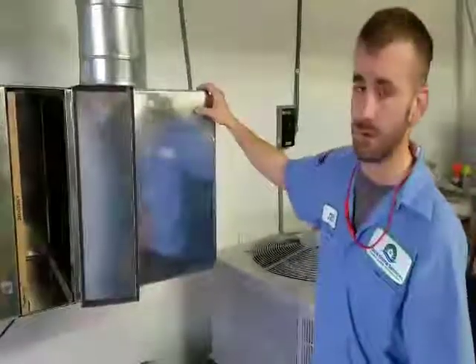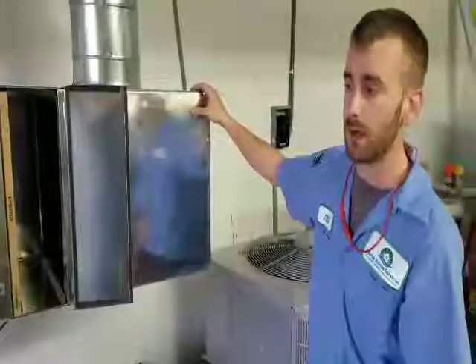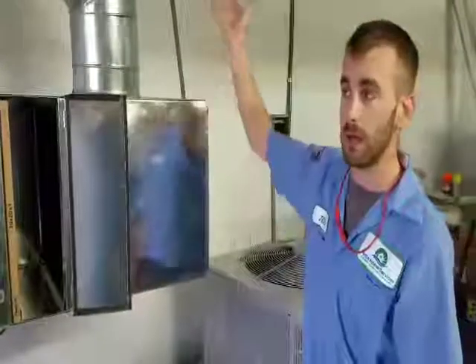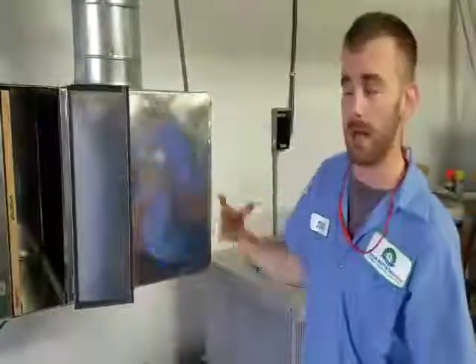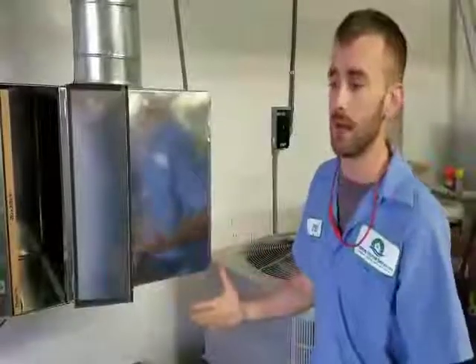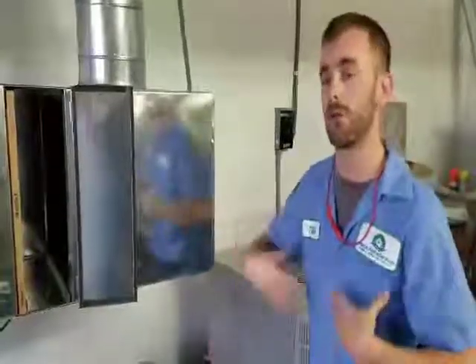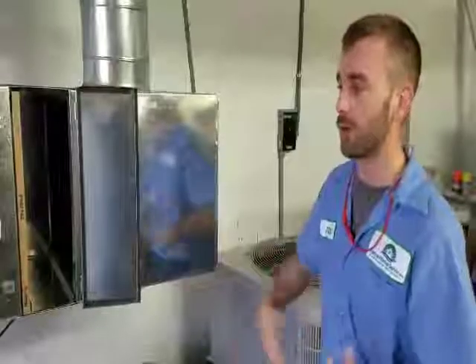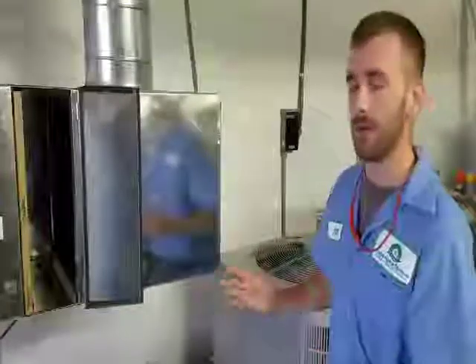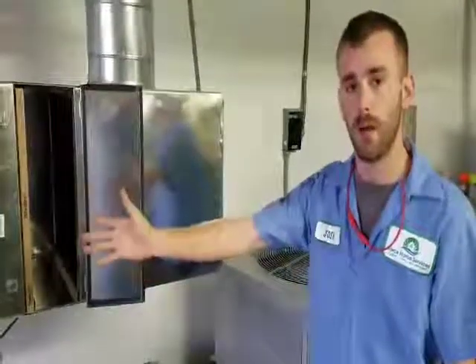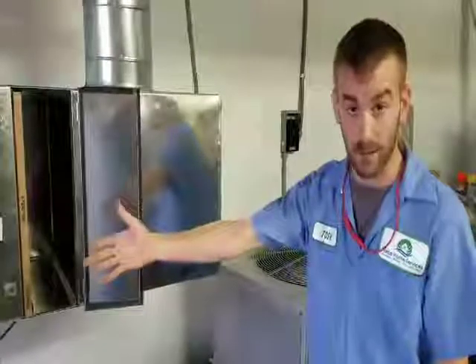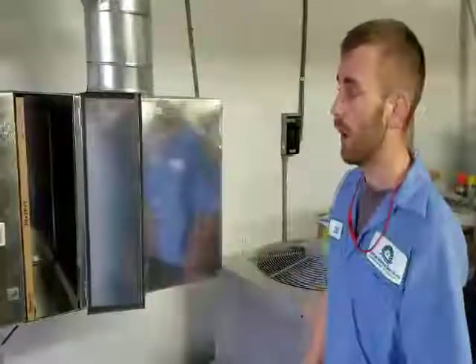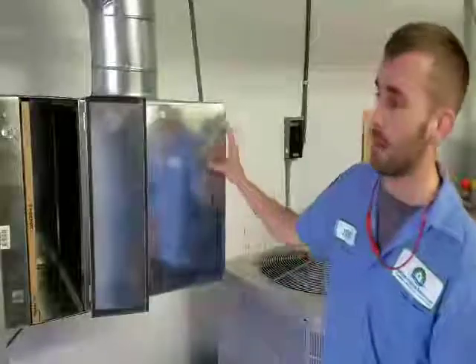A couple ways you can tell if your system is lacking return or not. If any of your return grills located on your ceiling or near your baseboards are making a howling noise, that's a good indication that your blower motor is struggling to draw air. And if it's struggling to draw air, then you're not getting enough air across that heat exchanger. And by the way, the number one reason for a cracked heat exchanger is poor airflow. So there are some things that I want to go over.